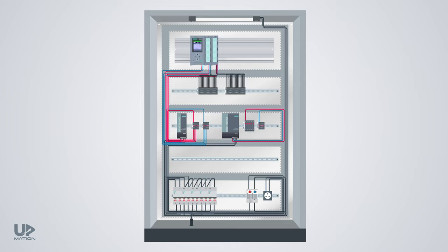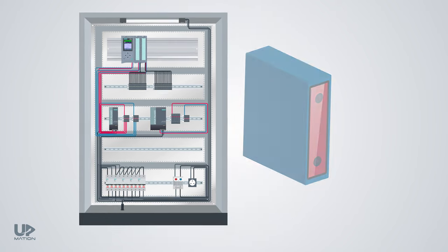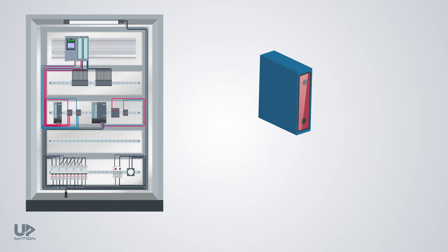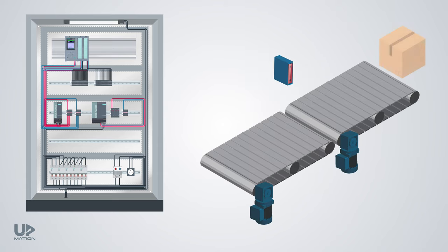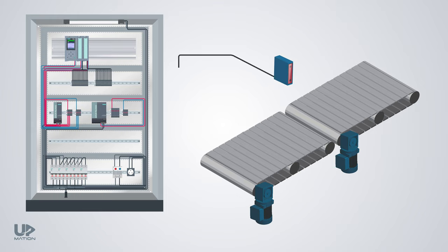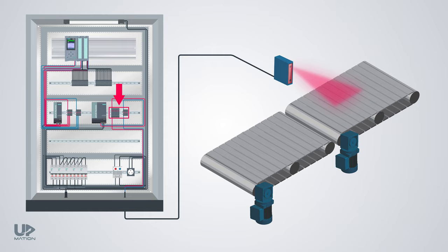Now let's have a brief overview of how to connect a sensor to our control panel. Take this photoelectric sensor as an example that is installed adjacent to the conveyor and is supposed to recognize the boxes that are passing by on the conveyor. As this sensor requires power to operate, I'd connect the 24V to that from the second power supply's terminal box. It should return these 24V to the PLC input card in case it senses a box or object in front of it. So I'm going to go ahead and connect a wire from the sensor to its corresponding PLC's input channel.